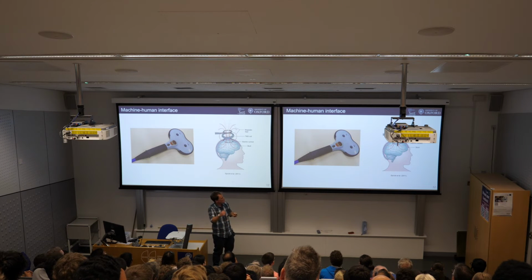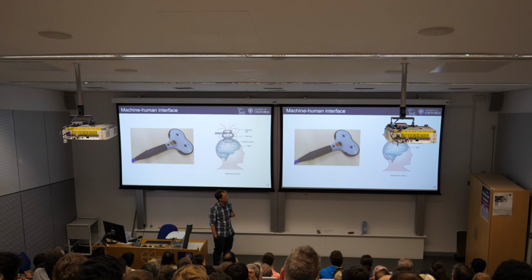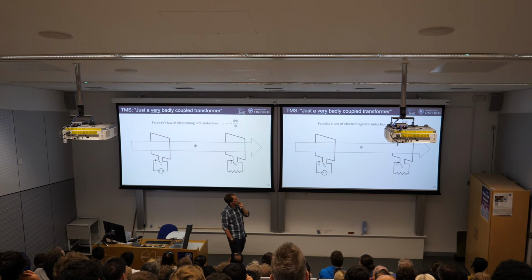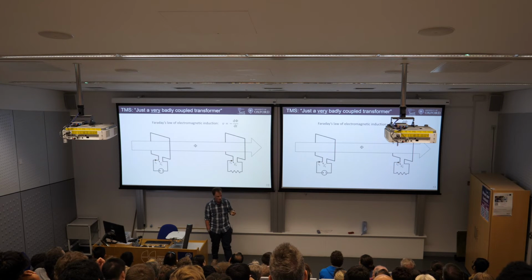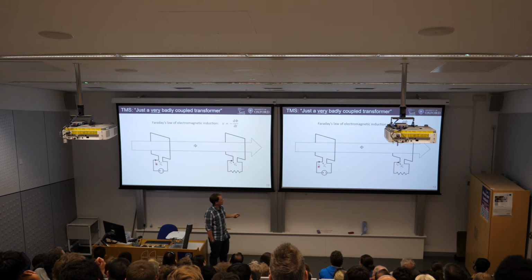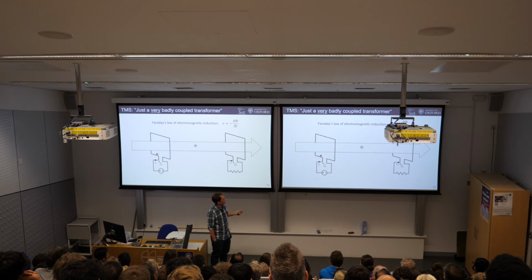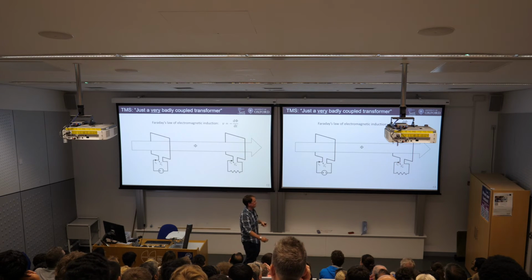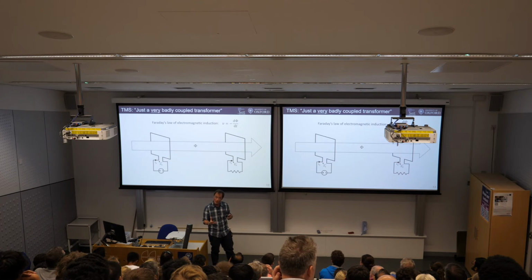So we take this coil, we put it next to the brain, and the field intersects the brain, and we'll get an effect, right? We'll talk a bit about that effect over the next few slides. So bringing it back to the engineering, what have we got? Well, we've got a glorified voltage source linked to a big coil. We're going to drive a magnetic flux through that coil. That flux is going to intersect someone's brain. It's going to induce a voltage in the brain.